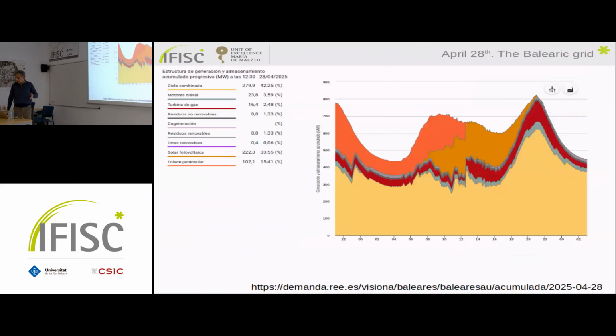To finish, the Balearic grid. That's the cable, it stopped at 12:30. It was carrying 100 megawatts, 15% of the total demand at that time, and 15% of the total generation disappeared when, in Spain, in a few seconds, all that happened. So what happens in the Balearic Islands?